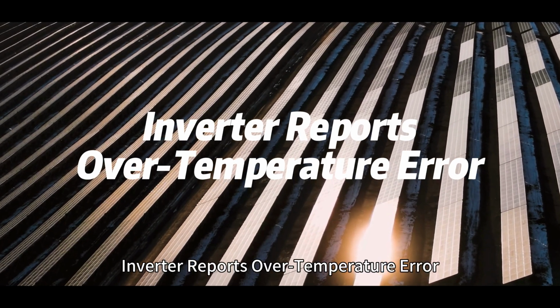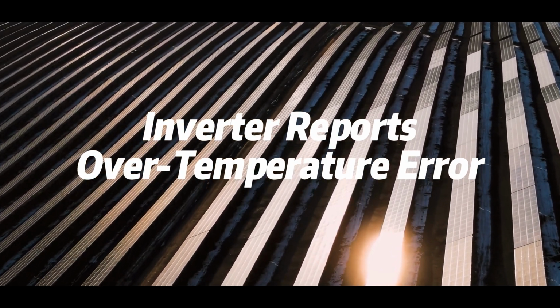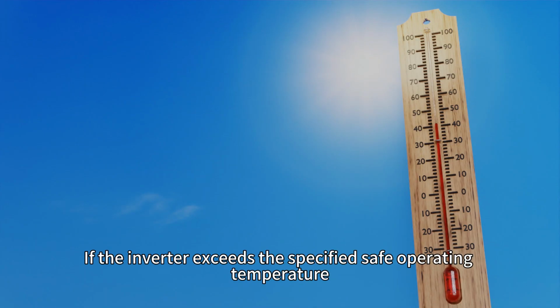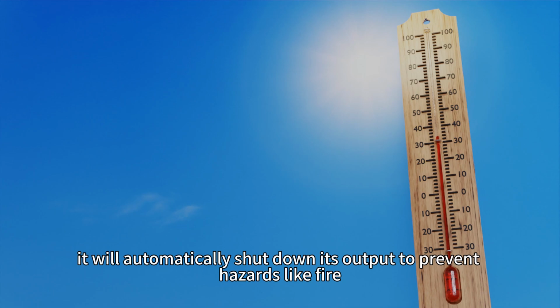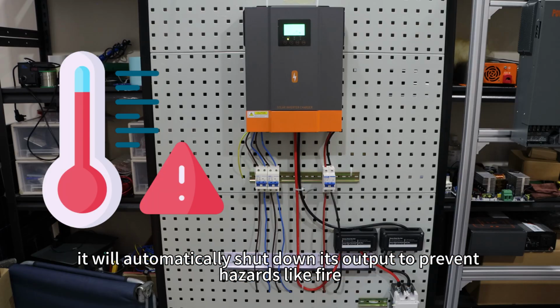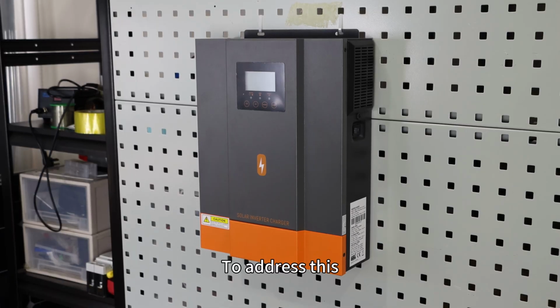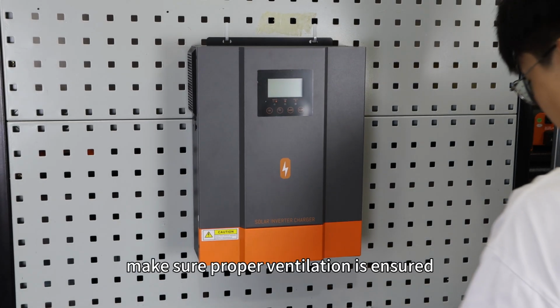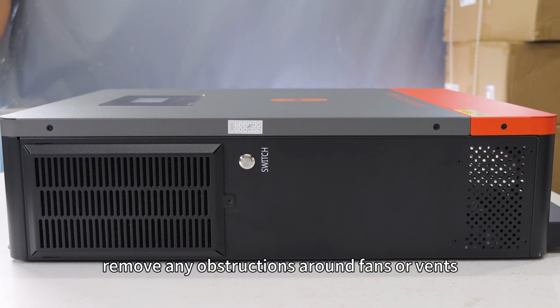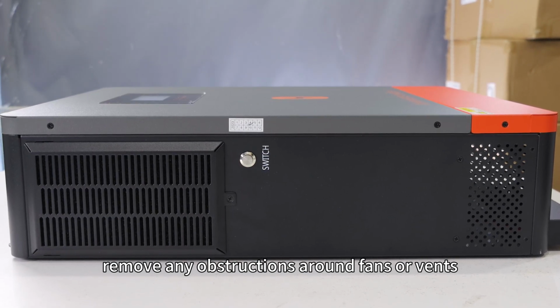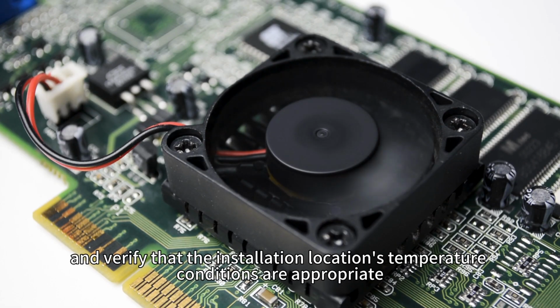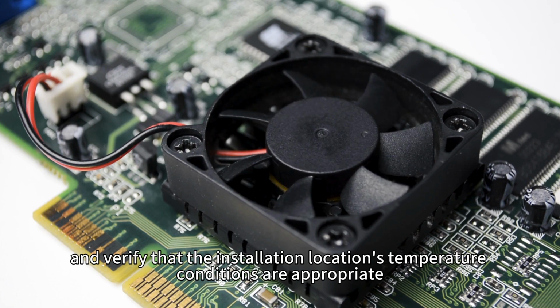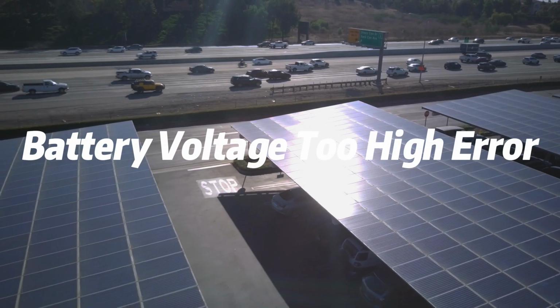Inverter reports over temperature error. If the inverter exceeds the specific safe operating temperature, it will automatically shut down its output to prevent hazards like fire. To address this, make sure proper ventilation is ensured. Remove any obstruction around fans or vents, and verify that the installation location's temperature conditions are appropriate.